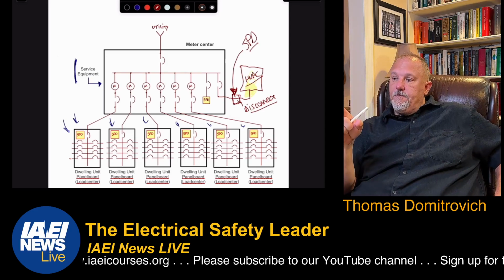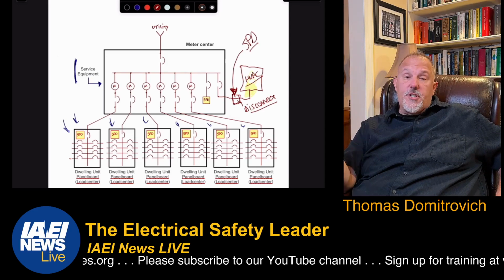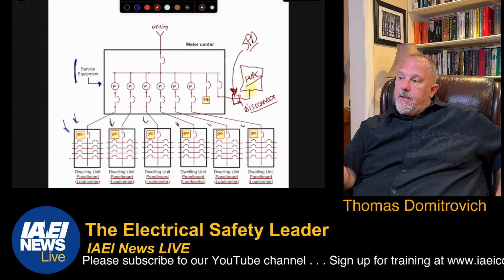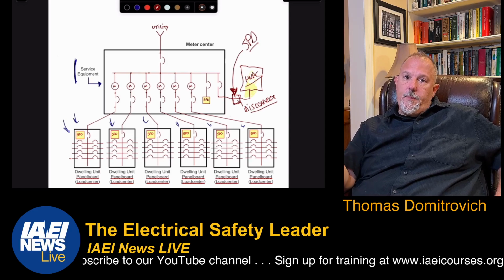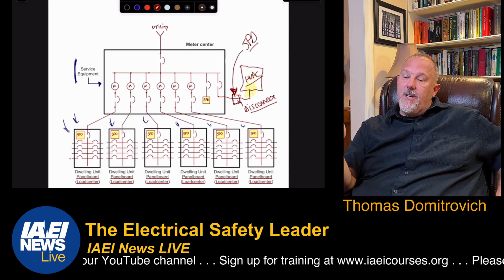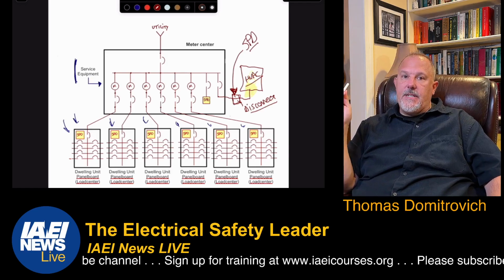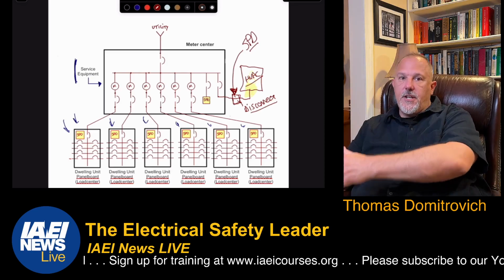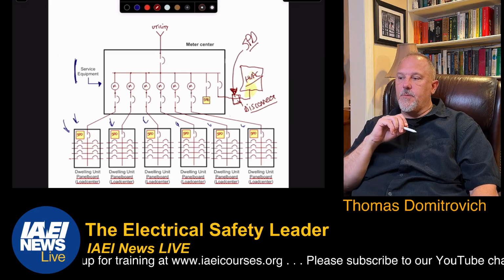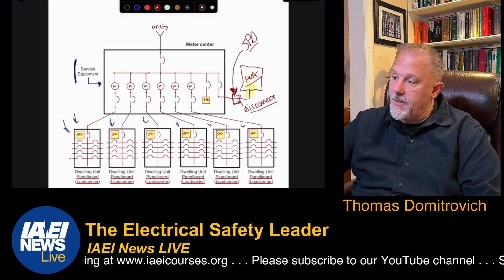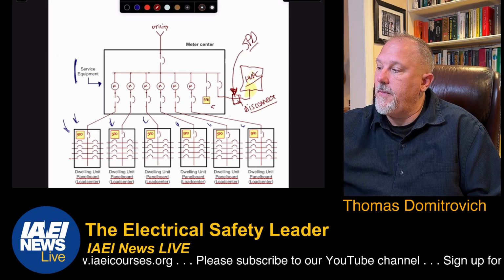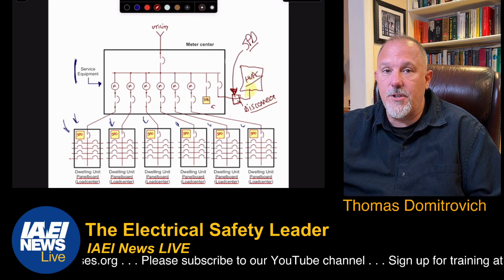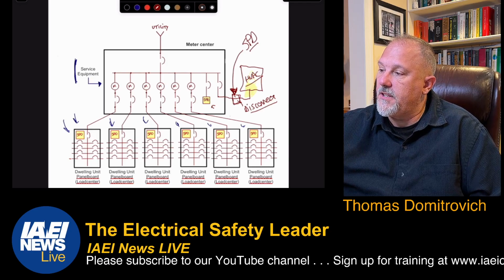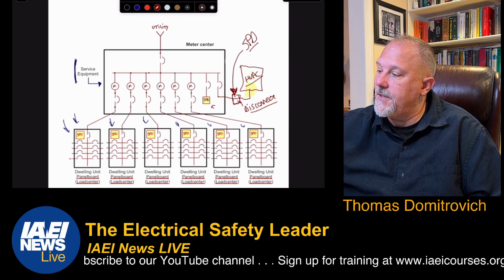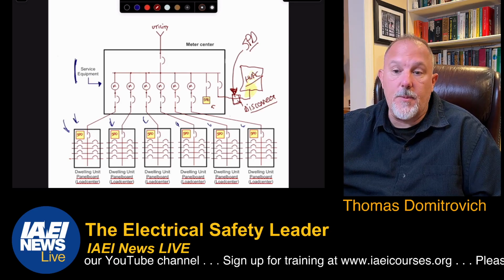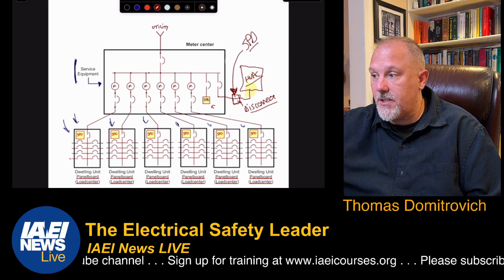to meet that exception. If there was no disconnect on that HVAC equipment and it was just a load and that was a branch circuit, then I would say you don't have distribution equipment. You are at the next downstream because the service feeds the HVAC directly. But if you go to a different disconnect and then go to the HVAC, that disconnect would have to have a surge protective device. And that was the situation we ran into. So we had to put a surge protective device in the service equipment, and then we also had it down here, unless we put surge over there, which we weren't going to do. So the surge protective device had to go at the service entrance equipment and at each of those next level distributions, which was down there at the dwelling units. So that's one application. That's a real world application.